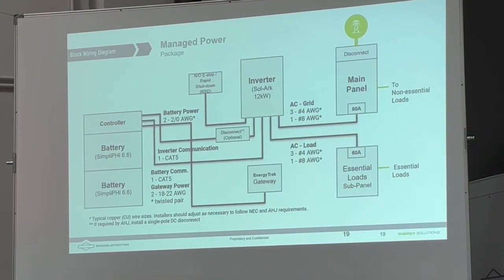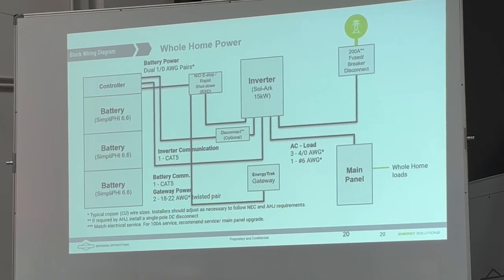So unlike other inverters where you would only be allowed to backfeed 20 amps or 40 amps on a 200 amp panel, you don't have to limit your breaker to a 40 amp breaker on a 200 amp panel or a 20 amp breaker on a 100 amp panel. Because of the PCS control, the extra level of certification that Sol-Ark has, right? Because you can limit it inside the Sol-Ark, and they've received that power control system rating, you're not limited on that breaker. Okay, so 15K, similar wiring diagram, but again, now we're going just straight through a fuse disconnect.